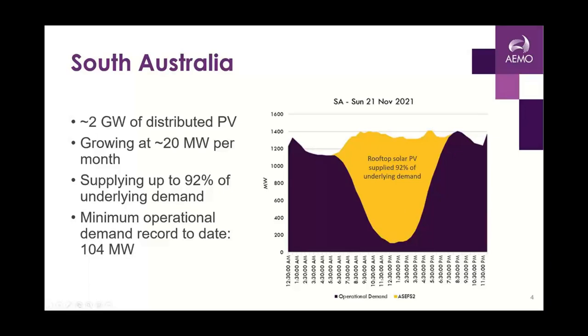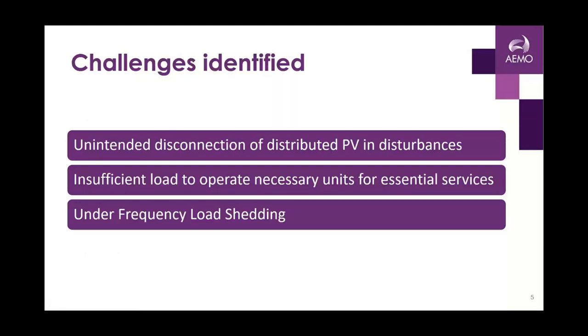So given that, we have seen quite a number of challenges that it's creating on our network. I have limited this presentation down to three, but there are quite a number of other areas. So looking specifically at the behavior of these distributed PV systems and how they have impacted the way we operate the power system. We've also seen that it's creating this huge diminishing of our actual load that we operate in, and what impact that has on operating the power system and providing for essential services. And then also how it's impacting our under frequency load shedding service.